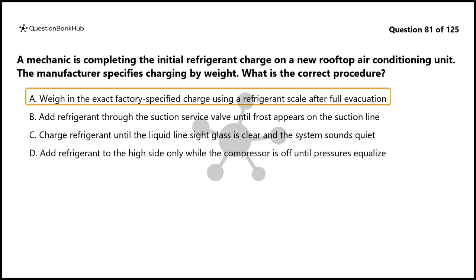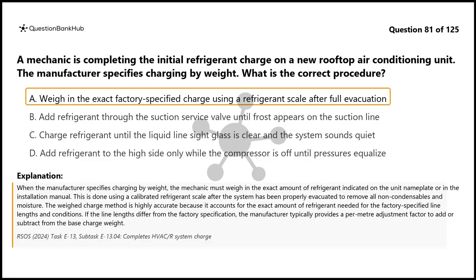The correct answer is A. When the manufacturer specifies charging by weight, the mechanic must weigh in the exact amount of refrigerant indicated on the unit nameplate or in the installation manual. This is done using a calibrated refrigerant scale after the system has been properly evacuated to remove all non-condensables and moisture. The weighed charge method is highly accurate because it accounts for the exact amount of refrigerant needed for the factory-specified line lengths and conditions.